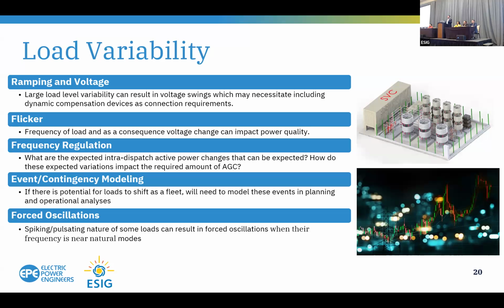That's been discussed in the industry, relating down to forced oscillations. Large language models can potentially have a spiking nature to their consumption, and the read and write have different load patterns with them. If it starts to happen on a regular cadence, every 3 seconds, every 4 seconds, and if you're in the Eastern interconnection, 0.25 mode is scary, 25 hertz mode is scary. You start to consider the impacts of having these collectively work towards a potential forced oscillation on the system.